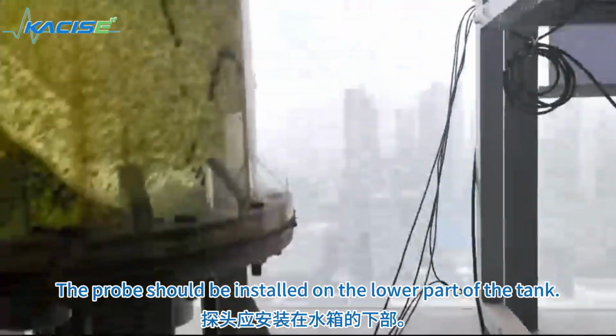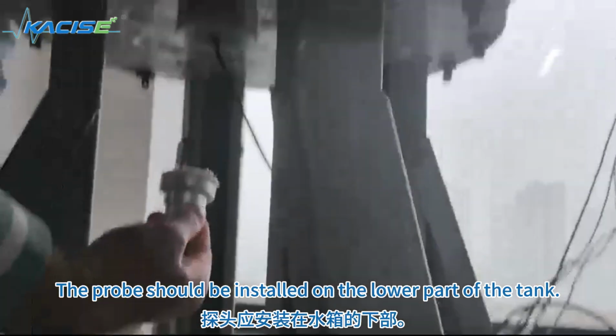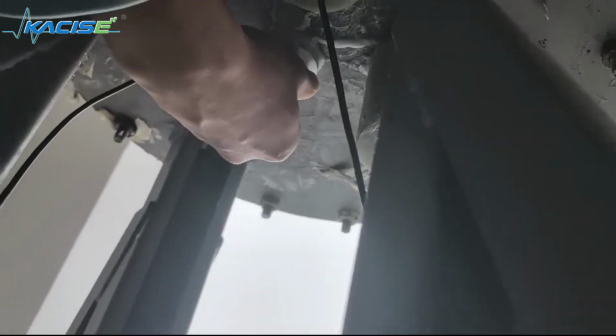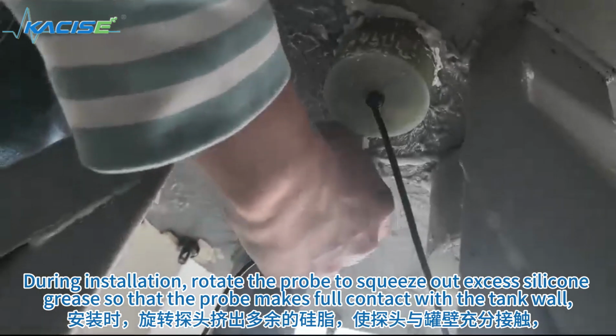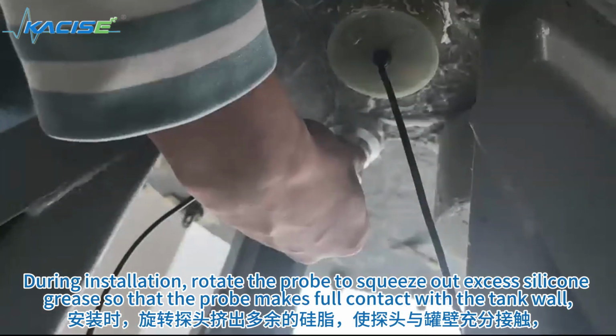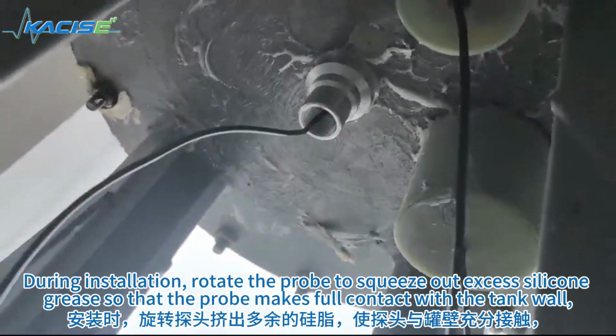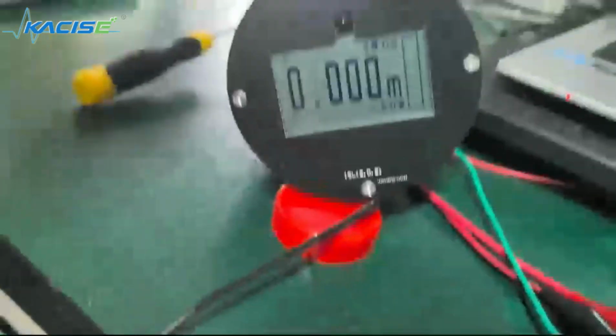The probe should be installed on the lower part of the tank. During installation, rotate the probe to squeeze out excess silicone grease so that the probe makes full contact with the tank wall, ensuring better measurement performance.